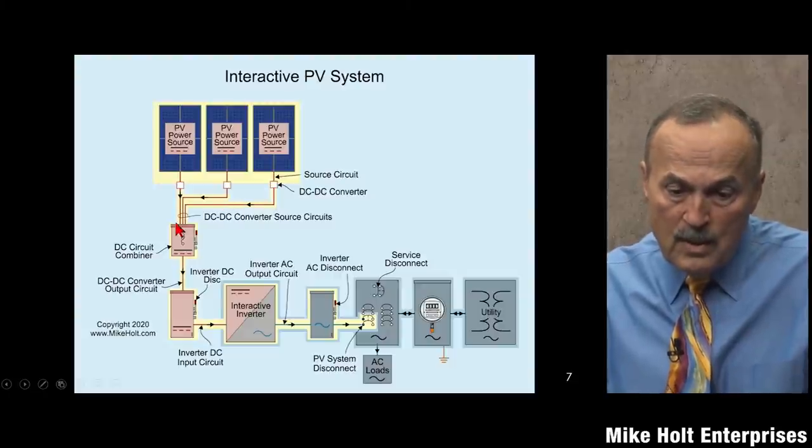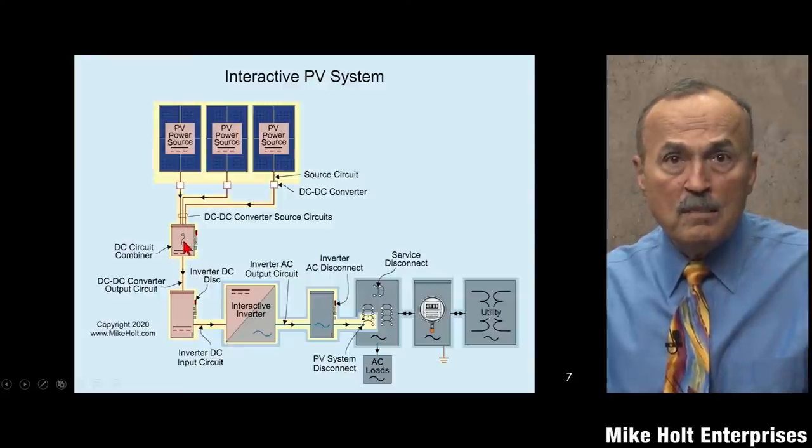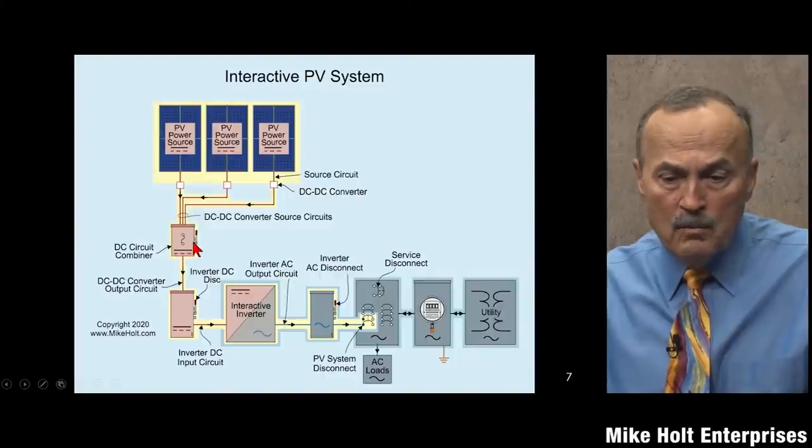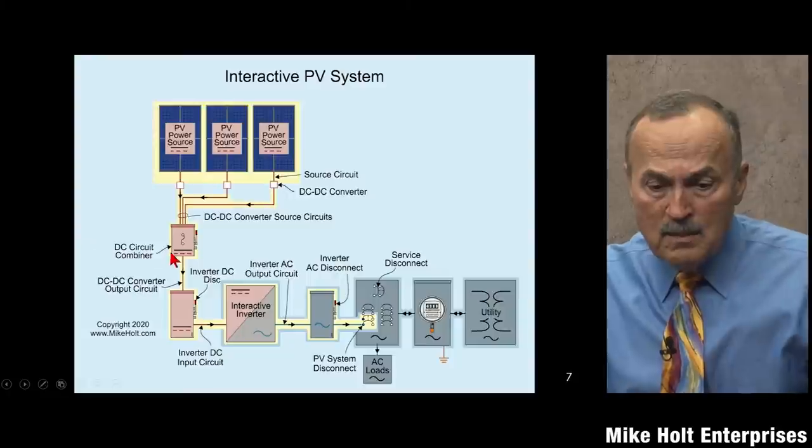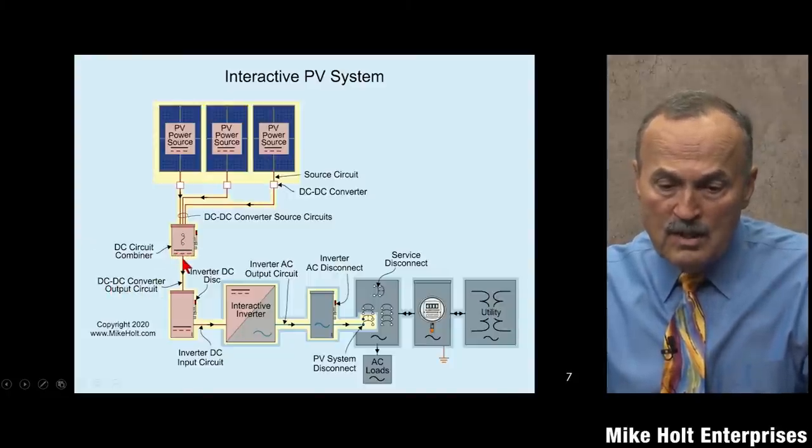You bring multiple circuits together into a combiner. Instead of running all those wires back to the inverter separately, you put them in a box and combine them. So six circuits of two wires each go into the combiner, and then you just run two conductors - bigger, because it carries the combined power - but it's much easier than running six separate circuits all the way back.